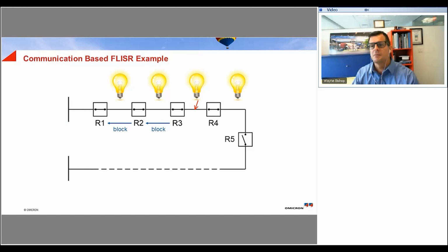So if we have, let's say, a fault occurring between R3 and R4, of course, R1, R2, and R3 will all detect this fault. What will happen is, because R3 is the closest recloser to the fault, it will send a blocking command to R2 and then subsequently to R1. Once recloser 3 trips and opens, we see that the customers beyond that will be out of service. The normally open tie recloser will then be issued a command to close, therefore restoring customer service to the customers between reclosers 4 and 5.